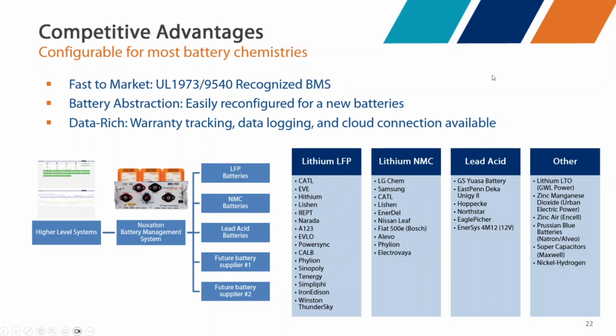This whole specification controlled design is made possible by our BMS, or any third-party BMS. The Nuvation BMS is highly configurable, so it allows you to use different cell chemistries and cell types. If there are different requirements from different providers, we can configure our BMS to work with them. It uses the same hardware, so there's no hardware change, just a software configuration change—something we can do, or our customers can do themselves. This is important because all the higher level system sees is a Nuvation BMS; it doesn't know what's underneath. We can abstract the whole layer below of what the batteries are doing, and also meet safety requirements.